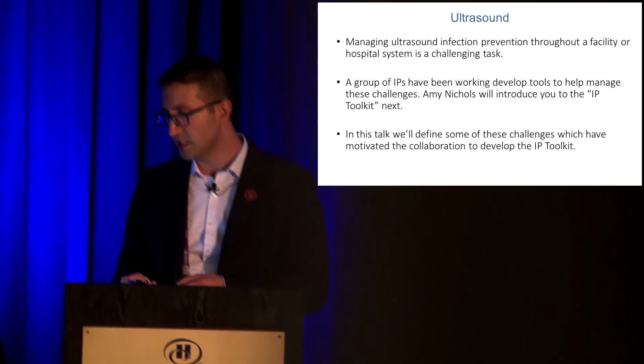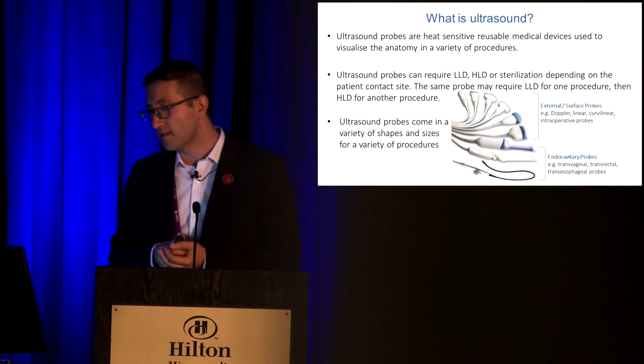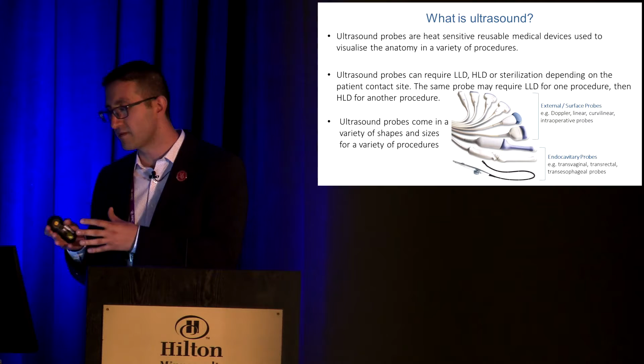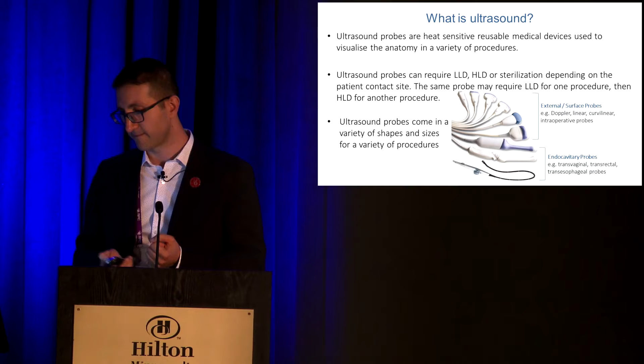Okay, so briefly, what is ultrasound? We know ultrasound probes are heat-sensitive, reusable medical devices. They are used to visualize the anatomy in a variety of procedures. These probes could require low-level disinfection or high-level disinfection or sterilization, and it really depends on the contact site, and that's key. So just keep in mind where that probe is, and that'll lead you down the right path. There are typically 2 categories of ultrasound probes: endocavity and external surface probes. And, of course, they come in various shapes and sizes.